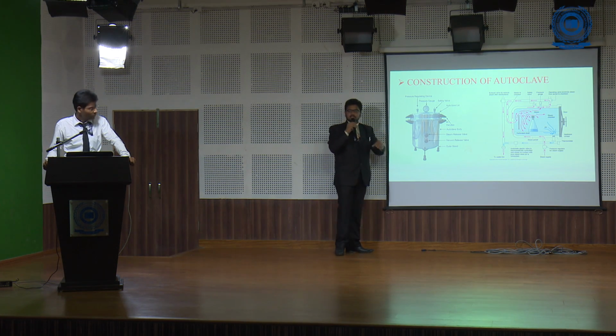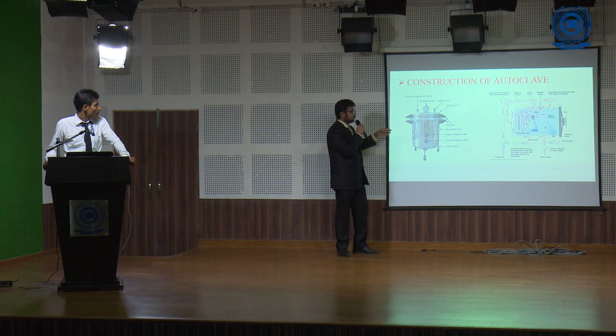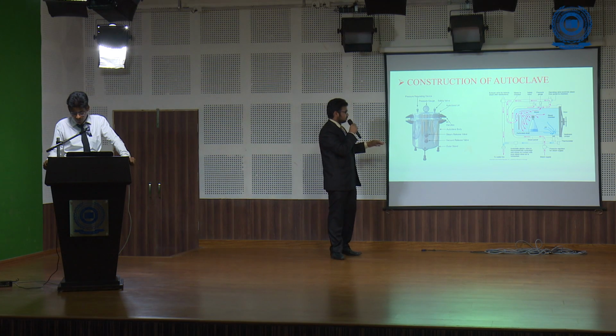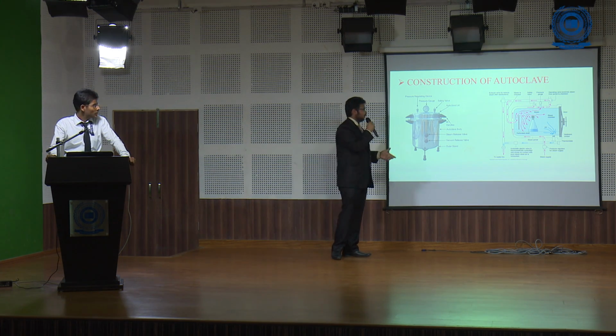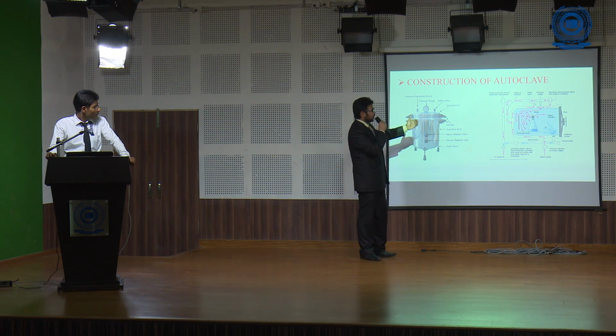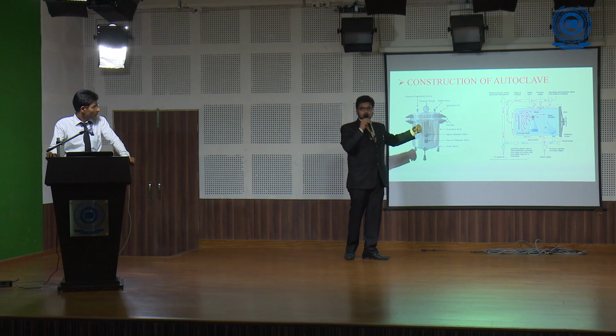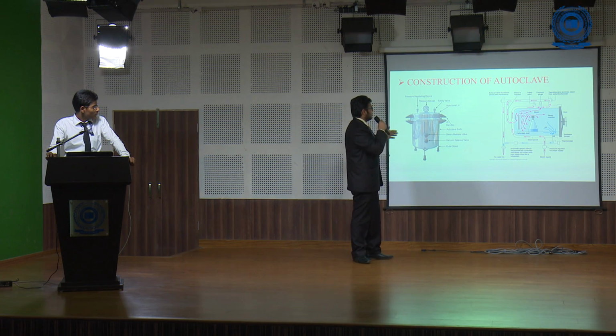The autoclave body protects the inner part of the autoclave, and a steam releasing valve and a vacuum releasing valve are also present to release the excess steam and vacuum. An outer stand is also given to stand the autoclave at any place in our laboratory. And this is an innermost view of the autoclave, so that you can understand how the autoclave actually works from inside.